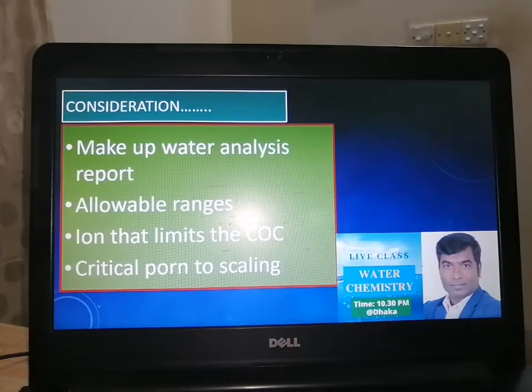So what do we need to consider to find out the critical ion for any water? First, we must have the makeup water analysis report. For example, if I want to establish a plant, design a utility system, or purchase a boiler, cooling system, or generator at a selected site, my primary task is to get a sample of their makeup water or available water source, analyze it, and obtain a correct makeup water analysis report.